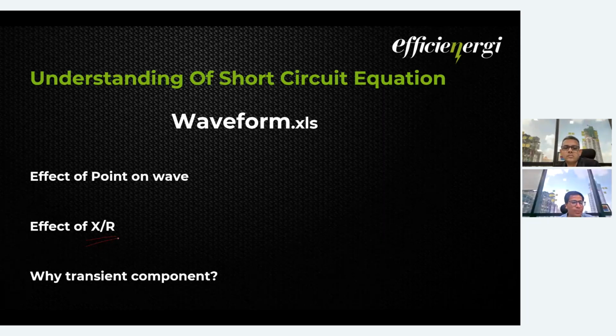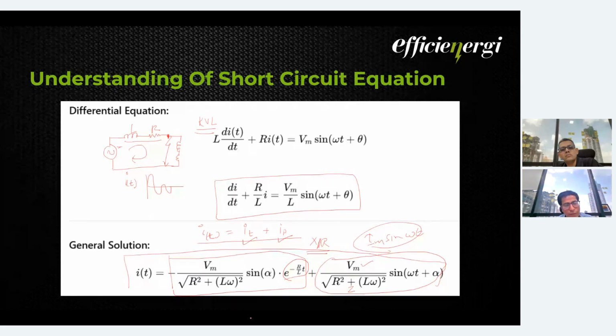Normally this is very important, because when we design any transformer, there is a certain X by R that we can ask for, to have a definite impedance of the transformer, so that the device duty of the component on the secondary side can be altered or reduced. And lastly, we'll see why the transient component is there. Everybody must have this question of where this DC component comes from. Now, if you see this wave equation, this is the DC component. But how and why it is there in the circuit, I think very few must know.